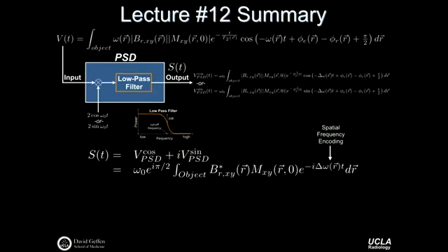And so this is what we're left with trying to work out for maybe the first 20 or 30 minutes of lecture today: how we combine these two phase-sensitive voltage signals. It's relatively straightforward. We're just going to add them together, treating one as the real component and the other as the imaginary component. In doing so, we get a complex signal that tells us about the state of the transverse magnetization vector. So we do finally end up with a vector-based quantity, which is useful because the magnitude and the phase are important things to us in MR. We'll work through this just now.